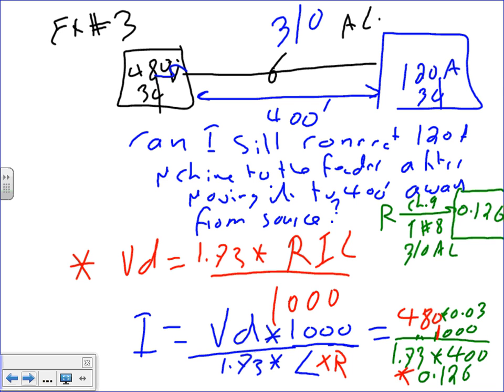Okay, did we miss anything? Ryan, my friend, I have the voltage right the second time, not the first time: times 0.03 times 1,000 divided by 1.73 times 400, and we got the R right the second time, 0.126. I need 2 gentlemen or a gentleman and a lady to agree. How much? 165. 165? Yeah, 165. Interesting. So we got one false up. Okay, so everything, 165 amp.